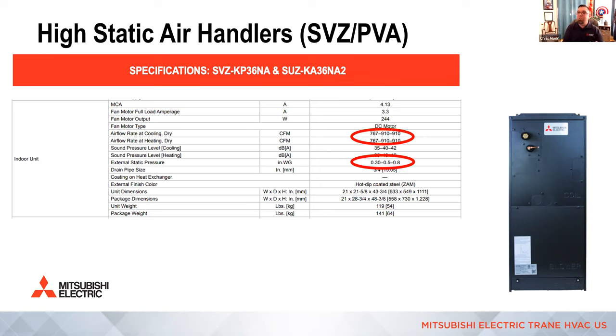amount of BTUs, or move the same amount of BTUs, with less volume of air compared to a unitary style product, right? So if you're familiar with, there were some great examples, Trane and American Standard, like Steve mentioned, they're typically 350 to 400 CFM per ton. Mitsubishi is normally closer to 300 to 320 CFM per ton. And that allows you to use typically smaller ductwork or a bigger system in smaller existing ductwork. Not drastic, but half a ton can easily be overcome by putting in a system that runs lower volume of air with higher heat output.